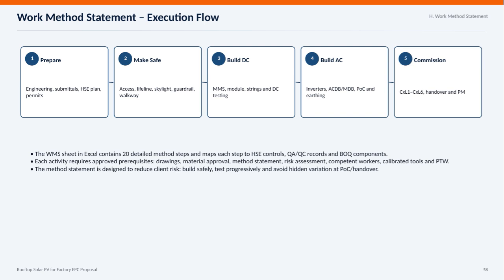Finally, the commissioning phase covers all levels of testing, handover procedures, and project management. The key element here is the WMS sheet, which details 20 method steps and links each to HSE controls, quality assurance, and the bill of quantities. Every activity must meet strict prerequisites like approved drawings, material approvals, risk assessments, trained workers, calibrated tools, and permits to work. This method statement is designed to minimize client risk by ensuring safe construction, progressive testing, and avoiding surprises at the point of connection or handover.